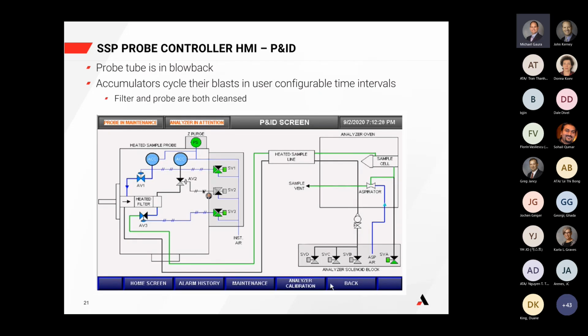And once a blowback is initiated, you can see that the notification pops up that the probe is in maintenance. The analyzer is no longer reading a sample, because the controller has given it a heads up. And this is actually the second portion. We've probably already gone through the first: the first accumulator has done its blowback of the heated filter. So that's already shot its 100 psi air through here and started to try and get any particulates that have accumulated on the filter out.